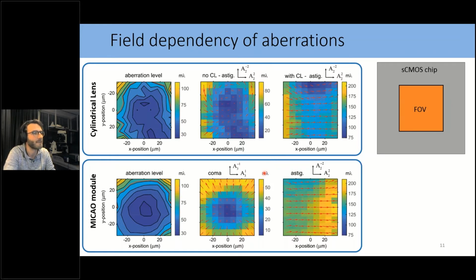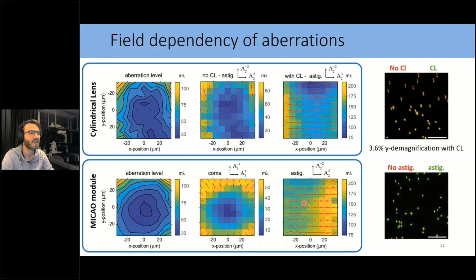If you now introduce astigmatism, either by putting the cylindrical lens in or by modulating astigmatism with the deformable mirror, we can see that the amount of astigmatism varies quite a bit with the cylindrical lens across the field of view. Not only the amount, but also the angle changes. Whereas this is much more homogeneous when you use the MicAO. Secondly, there's also a slight demagnification when you use the cylindrical lens, which is not present when you use the MicAO box. This is not a really big problem. Both of these effects you can correct for computationally, but you have to take that into account.